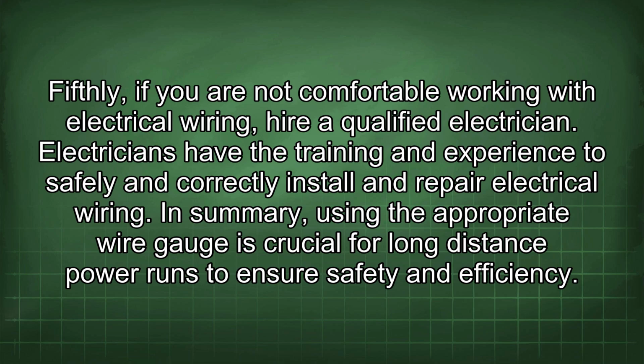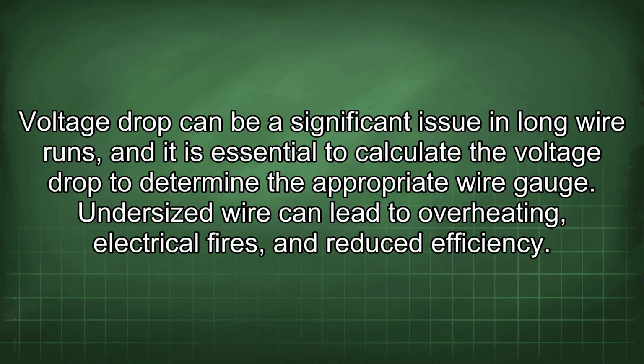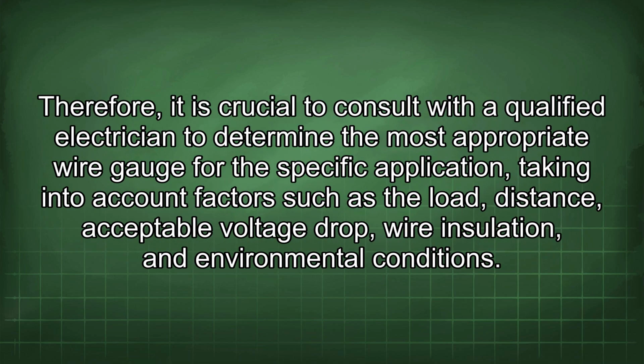In summary, using the appropriate wire gauge is crucial for long-distance power runs to ensure safety and efficiency. Voltage drop can be a significant issue in long wire runs, and it is essential to calculate the voltage drop to determine the appropriate wire gauge. Undersized wire can lead to overheating, electrical fires, and reduced efficiency. Therefore, it is crucial to consult with a qualified electrician to determine the most appropriate wire gauge for the specific application, taking into account factors such as the load, distance, acceptable voltage drop, wire insulation, and environmental conditions.